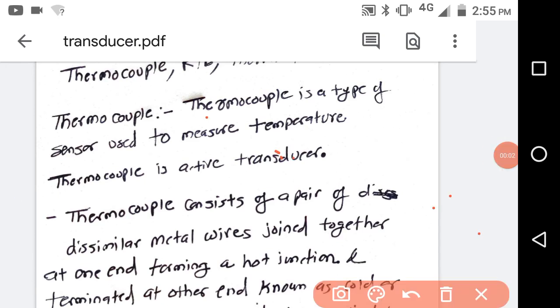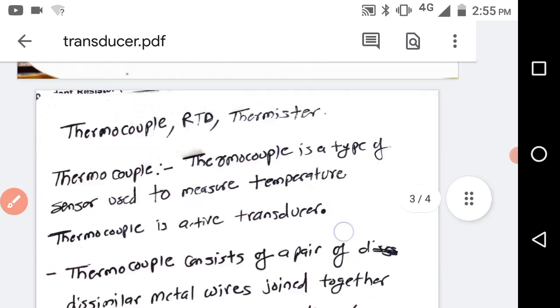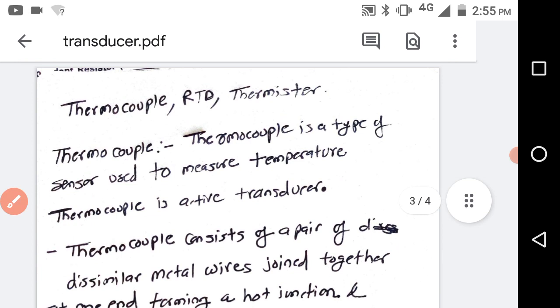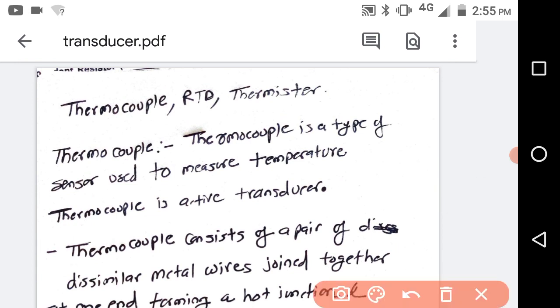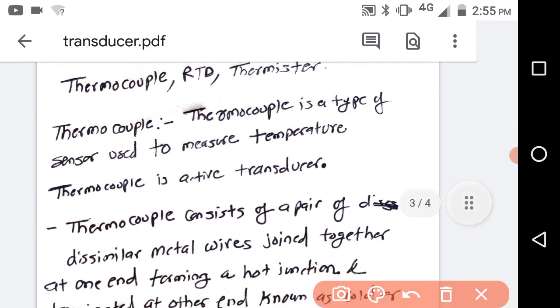Let us see in this video about temperature sensors. So we are going to see three temperature sensors or transducers. Those are thermocouple, RTD and thermistor. They are sensors and they can be converted to the transducer if you connect the external circuitry. So what is thermocouple? So first of all, thermocouple is an active transducer and RTD thermistor are passive transducer.